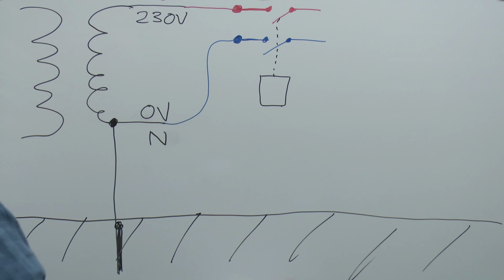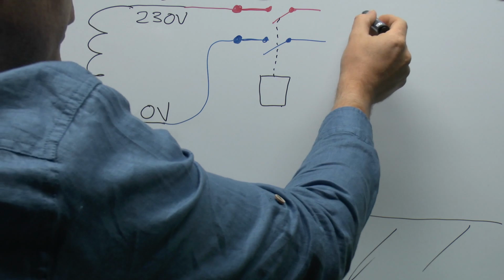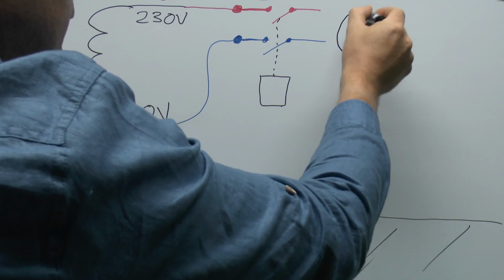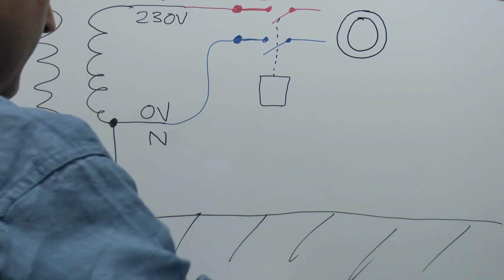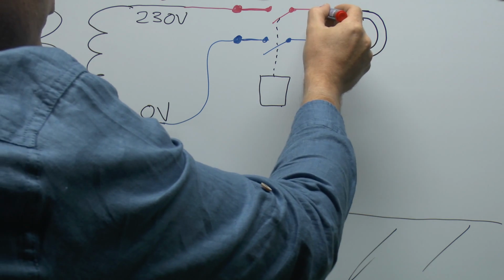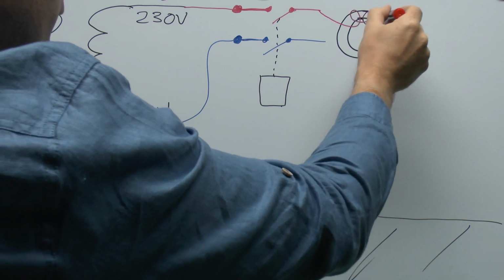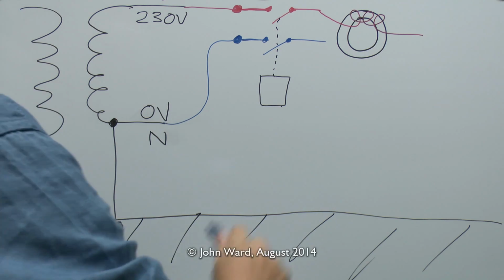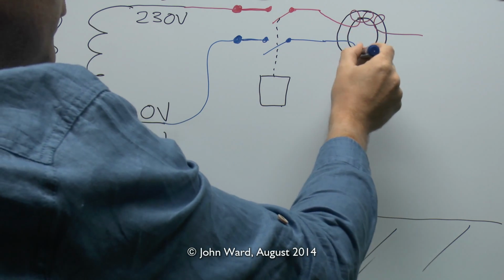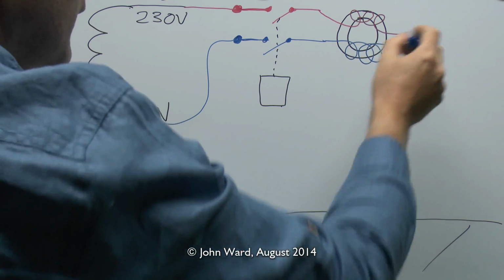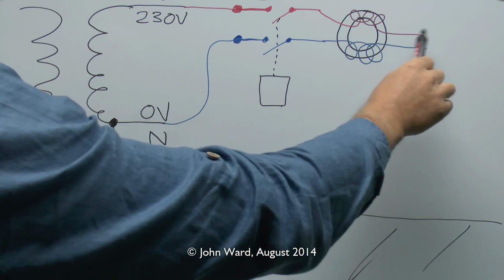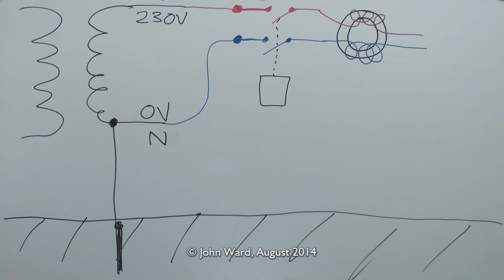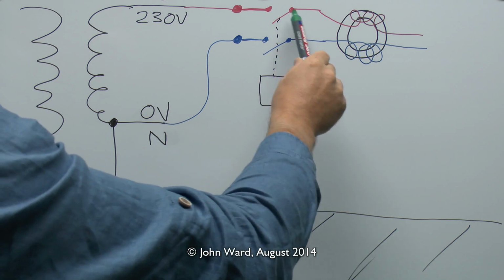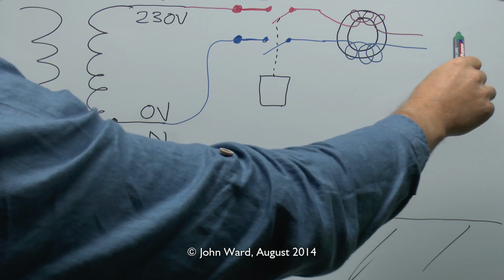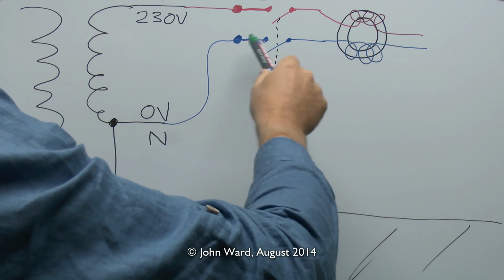And the actual sensing part is incredibly simple. In older ones it was just a magnetic core, and the two wires would come in and basically wind around the core, and of course the neutral would do likewise. And then this will go off to whatever load or equipment you have attached. So in normal circumstances the current would flow through here, through the coil on there, through to the load, and then return via the same path and back to the supply.